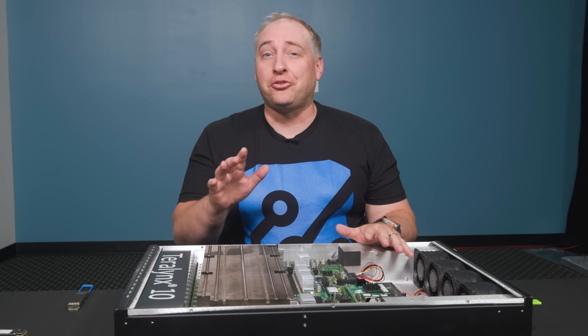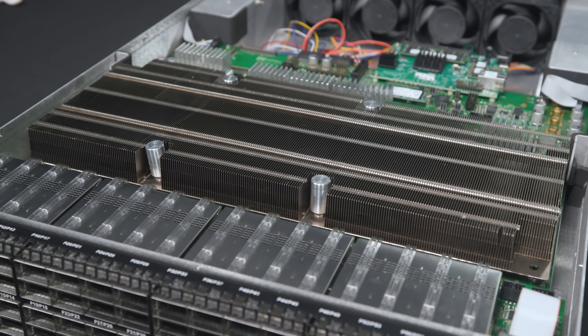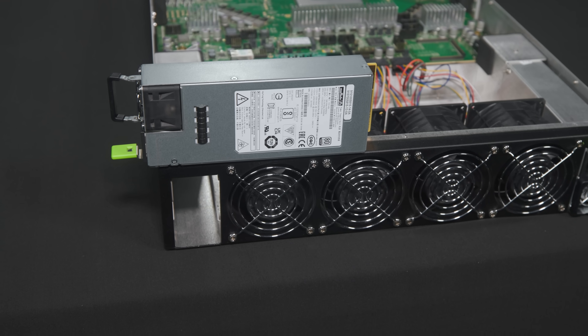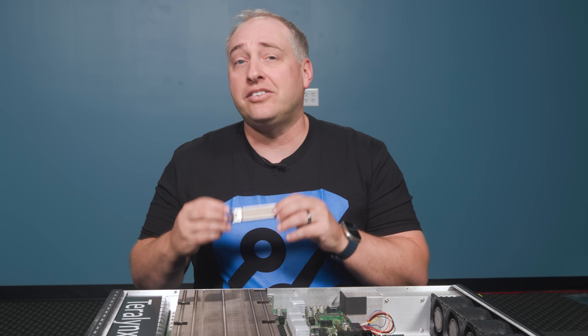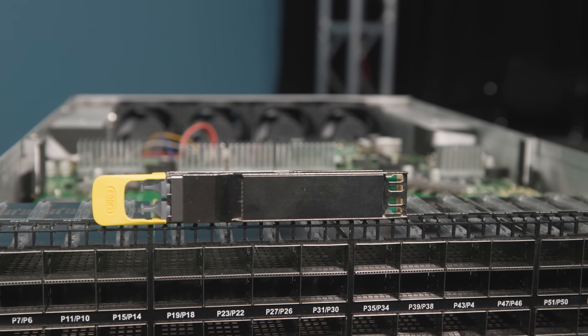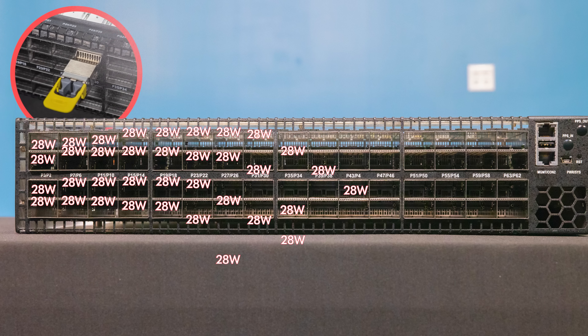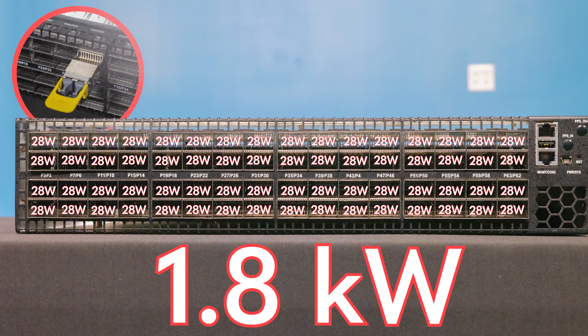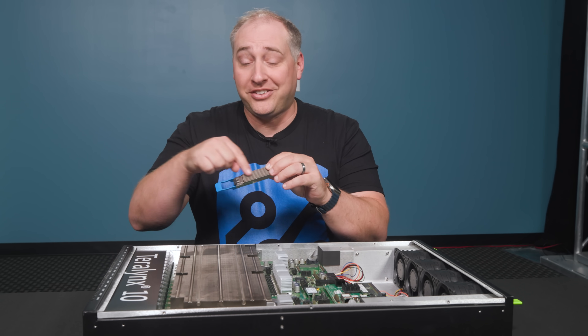These are no longer like two, three-watt devices — those days are long gone. Each of these OSFP 800 modules has a spec of up to 28 watts. If you have 64 of them, that means you have almost 1.8 kilowatts just of optical modules on the front of this switch.